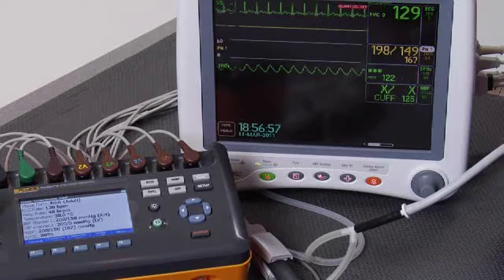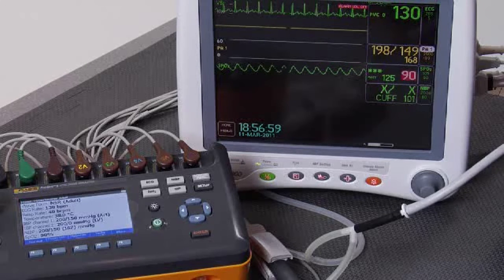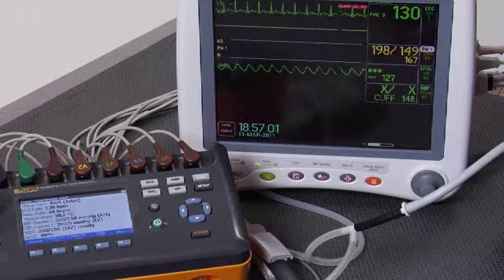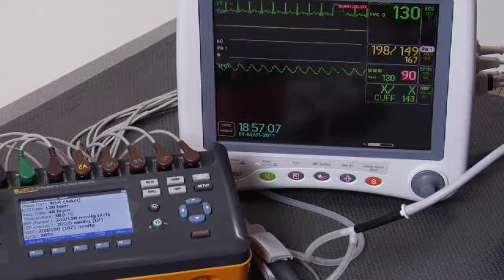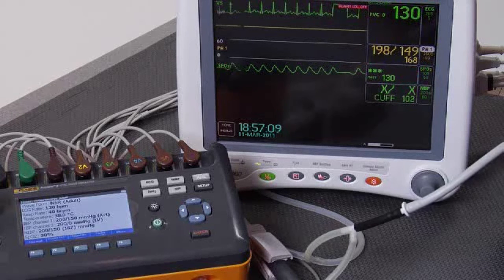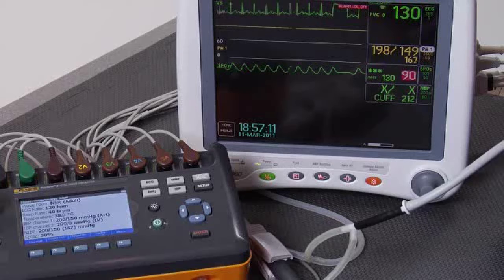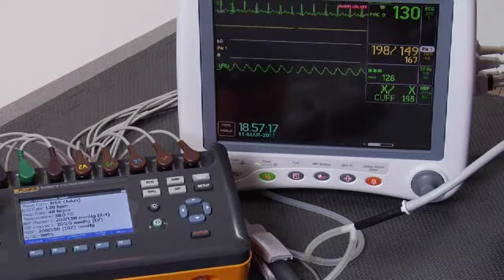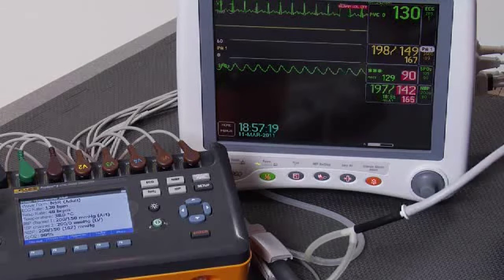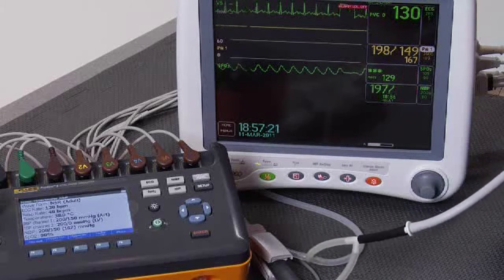In this case, we're looking for an ECG rate of 130 beats per minute, respiratory rate of 40. We're looking for an invasive blood pressure display of 200 over 150. We're looking for NIBP of 200 over 150 with a mean of 167, and an SpO2 reading of 90. And it looks to me like we've got all of those on the patient monitor.